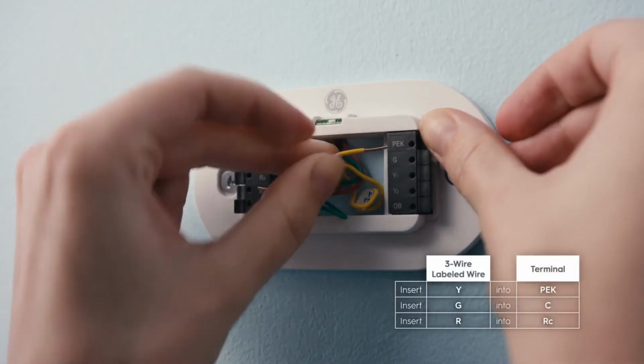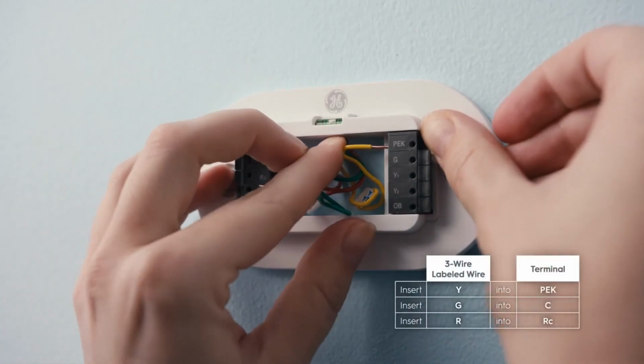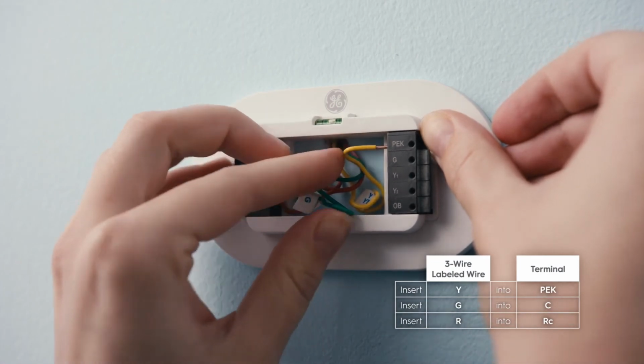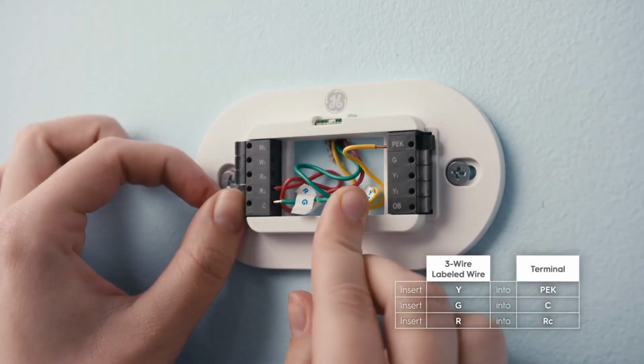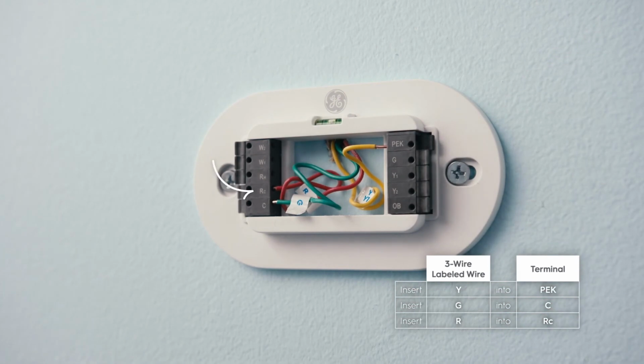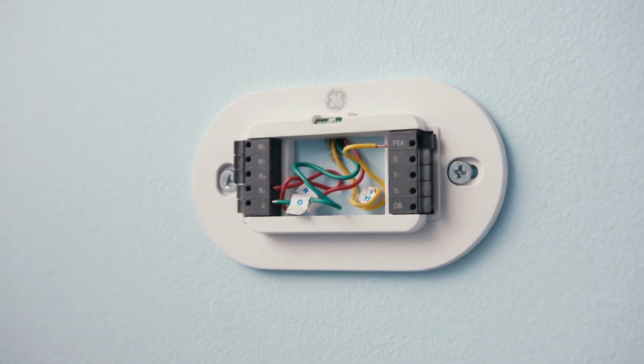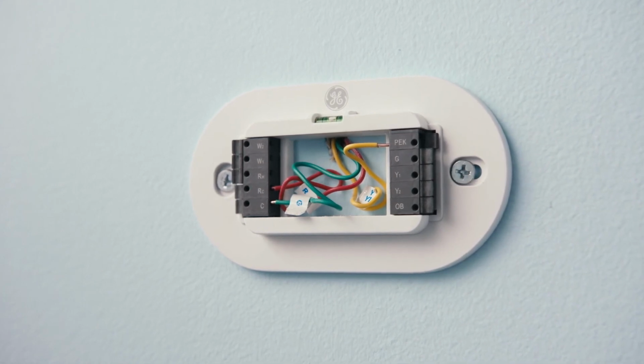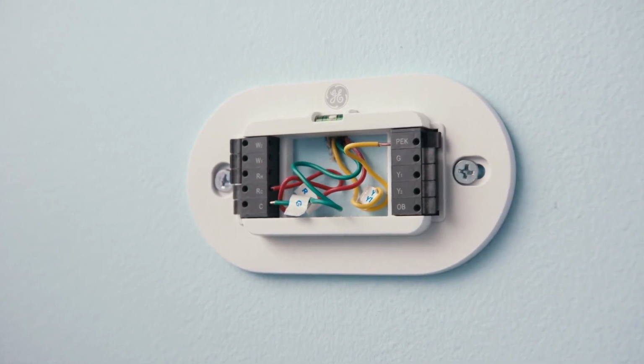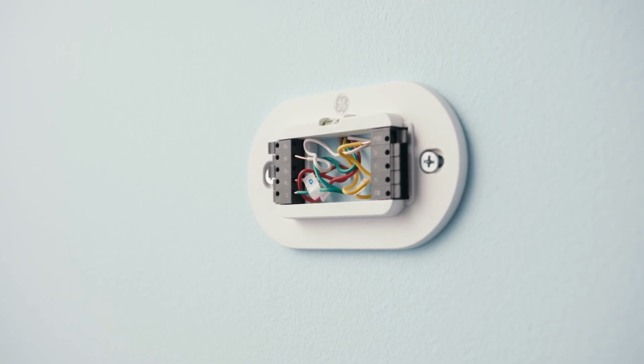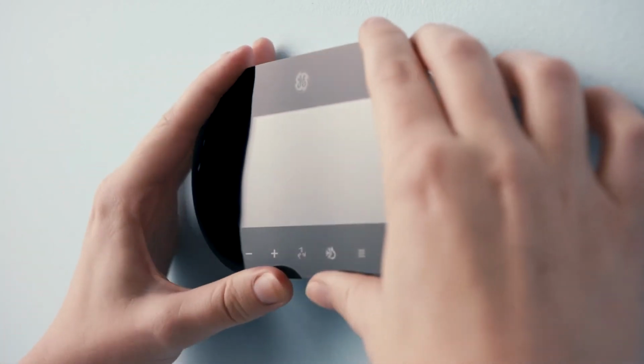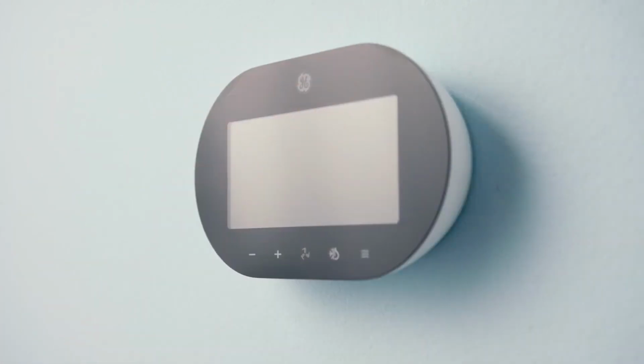For a 3-wire setup, wire Y or Y1 should go to terminal PEK. Wire G should go to terminal C, and wire RC or RH should go into terminal RC. Insert any remaining wires into their corresponding terminals on the backplate. Tuck any excess wire into the wall. Then, mount your new smart thermostat onto the backplate. The thermostat control buttons should be along the bottom. Once aligned with the backplate, gently push the thermostat on the sides of the screen until it clicks into place.